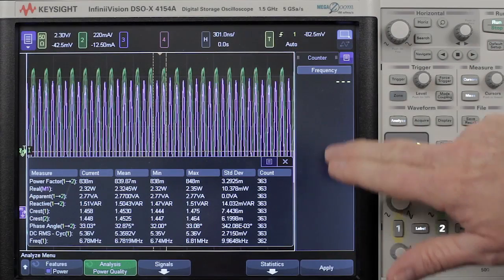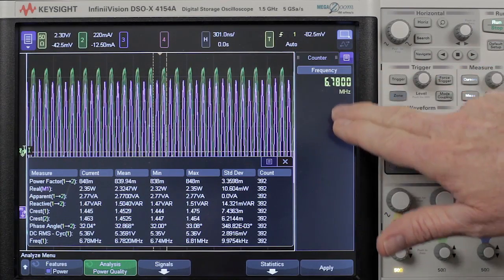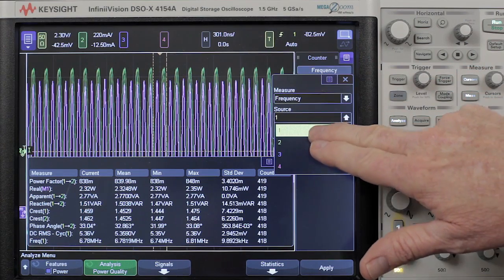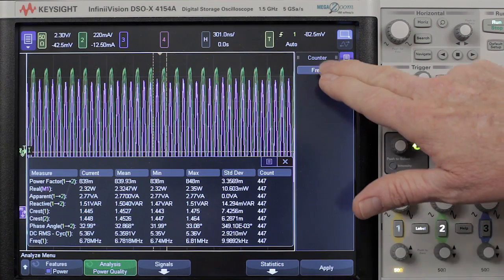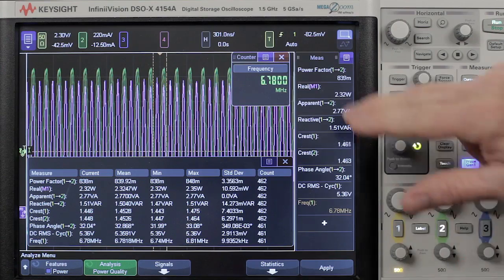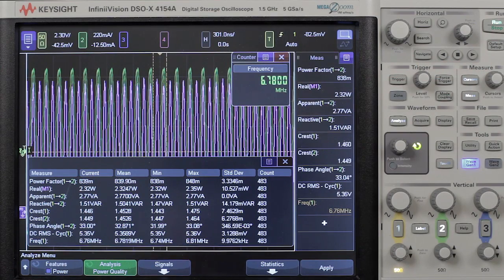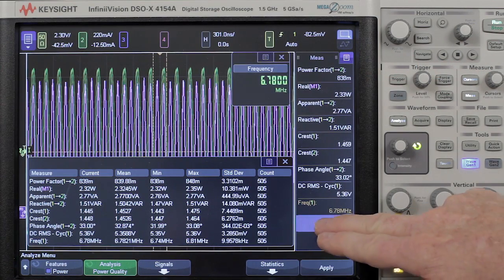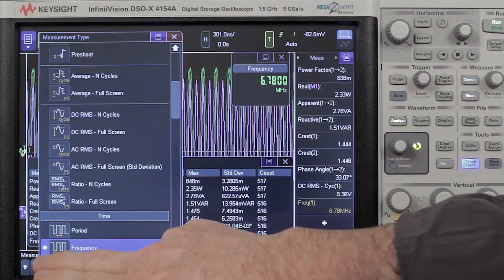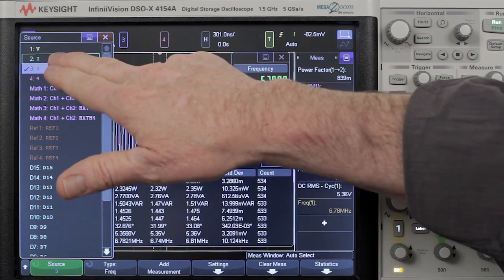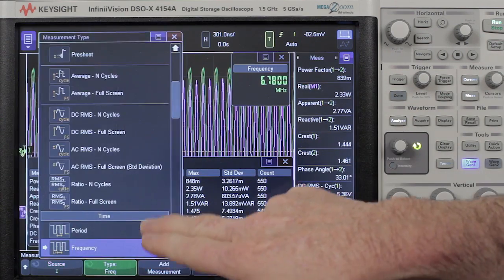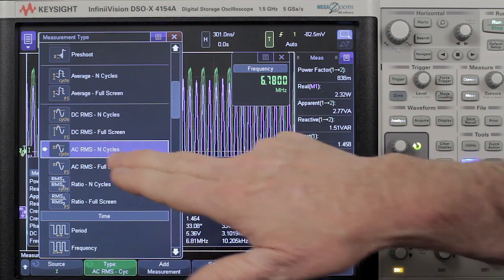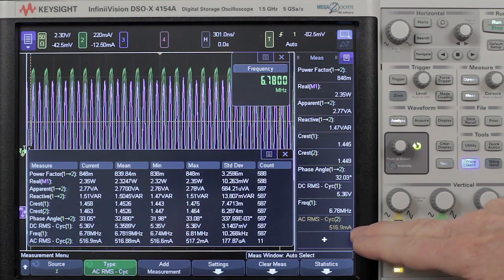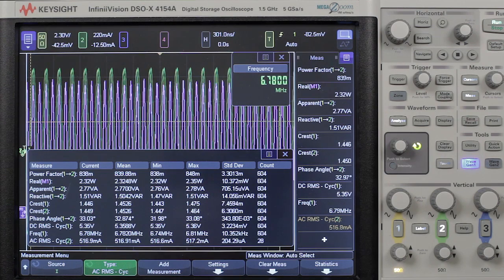Now we can add to it a counter measurement that will give us a more accurate measurement of the frequency. Let's do it on the current channel. Move that over to the side. So there we have a 5-digit frequency measurement, and we may want to add a current measurement. RMS current measurement. Select AC RMS in cycles, and there you can see we're measuring about 516, 517 milliamps.